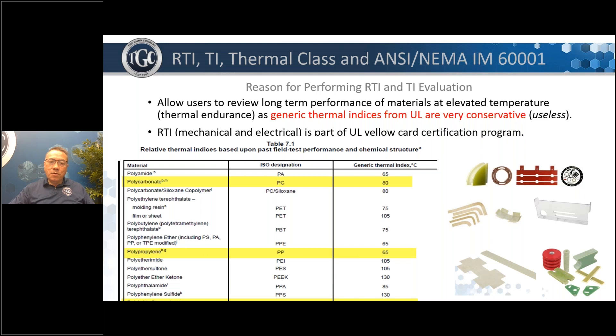That's just a little bit more than warm water, and we know that engineered grade polypropylene can do a lot better than that. Even very high-end material like PI — polyimide — we know it's a 200 to 220 degrees C material, but the generic RTI is only 130. So obviously, as a manufacturer, we do not like to use UL generic RTI.